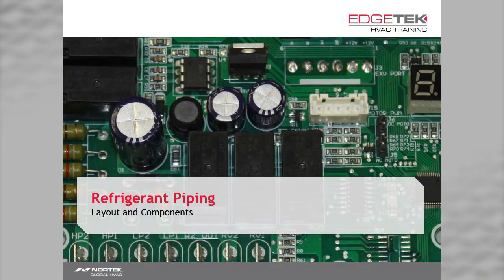So we're going to get into more of the nitty-gritty of installing a VRF system. The beauty of this being in video format is that if you miss anything, you can always rewind and watch it again. With a system that can use up to 984 feet of liquid line, you can imagine that piping is very important. With communicating equipment like this, it is also imperative that the system is wired correctly.